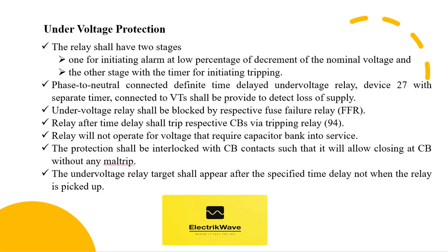The relay after time delay shall trip the respective circuit breaker via tripping relay. The under voltage relay shall be set such that the relay will not operate for voltages that require the capacitor bank into service; adequate margin shall be provided. The protection shall be interlocked with circuit breaker contacts such that it will allow closing of the circuit breaker without any mal-trip. The under voltage relay target shall appear after the specified time delay, not when the relay is picked up.